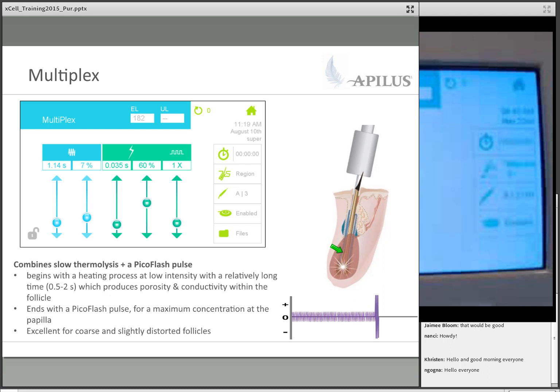The one thing to know with the Multiplex is that you have to press and hold down the foot pedal. If you don't hold it down, you lift it up too soon, it will interrupt the current. And so the machine will not just keep going like a light switch. If you lift your foot off right here, it's going to stop the pulse at this point here. So the Picoflash will never get delivered. Sometimes people work with the Multiplex, say it doesn't work, but they're not keeping their foot down until the actual beep happens. So let's go back to our webcam and I will actually go through a pulse of Multiplex here.